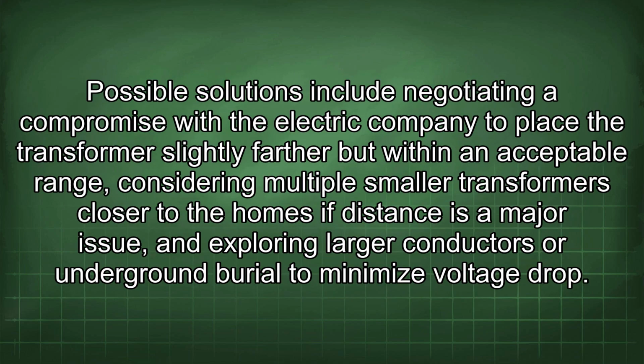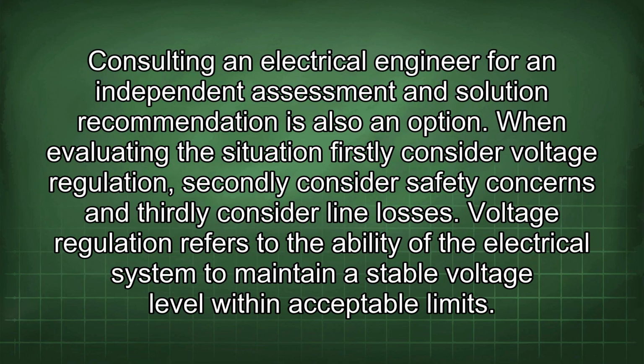Possible solutions include negotiating a compromise with the electric company to place the transformer slightly farther but within an acceptable range, considering multiple smaller transformers closer to the homes if distance is a major issue, and exploring larger conductors or underground burial to minimize voltage drop. Consulting an electrical engineer for an independent assessment and solution recommendation is also an option. When evaluating the situation, firstly consider voltage regulation, secondly consider safety concerns, and thirdly consider line losses.